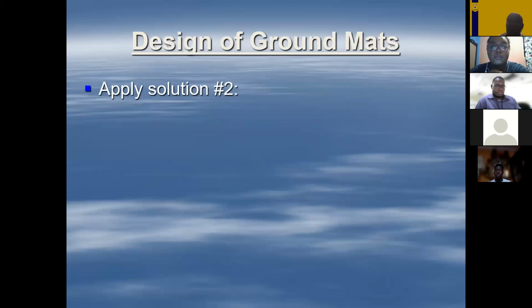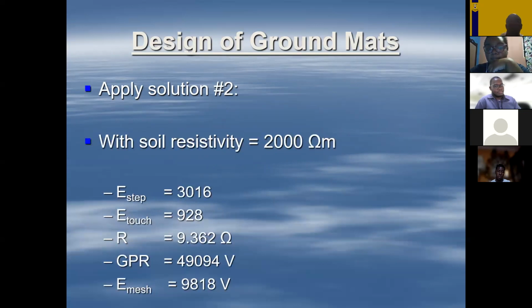If we apply the second option, bringing in crushed rocks, we get an overall resistivity of 2,000. The E-step goes up to 3,000, the E-touch increases to 928. But look at what happens to the mat resistance - it goes up by almost 20 times. So the ground potential is now 49 kilovolts, and the E-mesh, applying all the criteria we mentioned, comes down to 9,000.